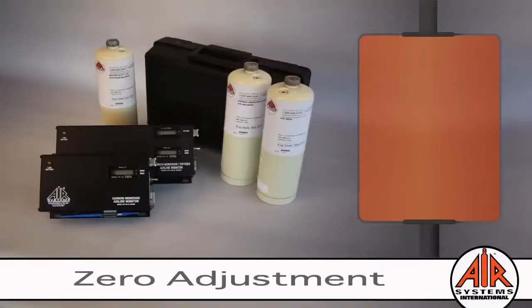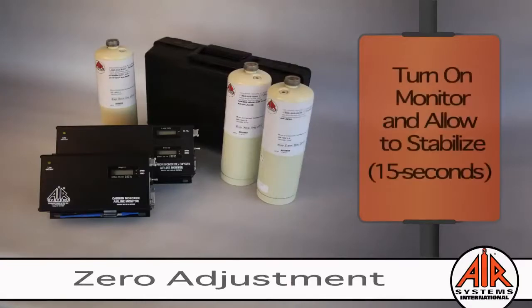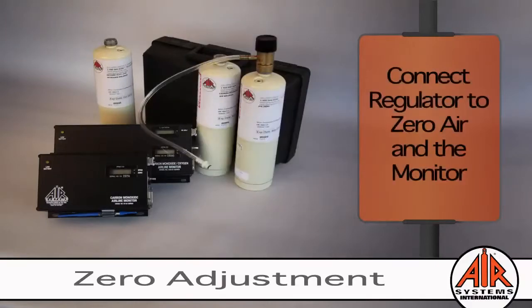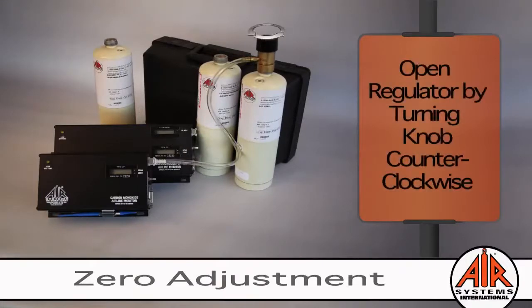The zero adjustment is the first of 3 phases in the calibration process. Now let's get started by turning the monitor on and allowing it to stabilize for at least 15 seconds. Connect the regulator to the zero air cylinder and then to the monitor. Open the regulator by turning the knob counterclockwise.